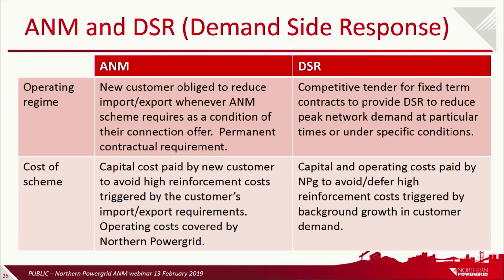ANM is all about customers being able to get connected quicker and more cheaply, but as a condition of that cheaper connection, because we've avoided the reinforcement, they agree to reduce their output when necessary, and that's a permanent contractual requirement for the lifetime of their connection. They need to factor that reduction in, and there's no payment made to them for it because they've got the cost saving in the initial connection charge.